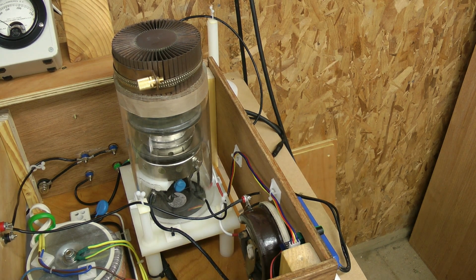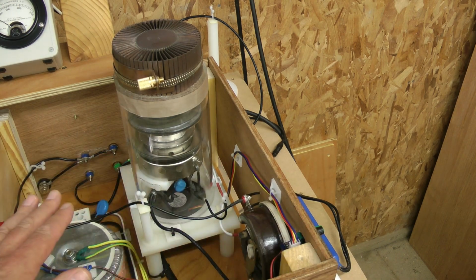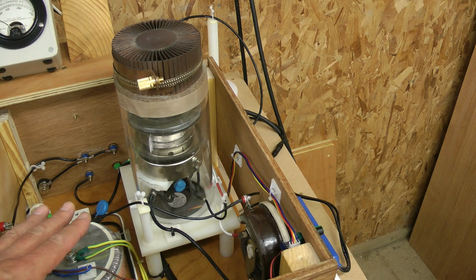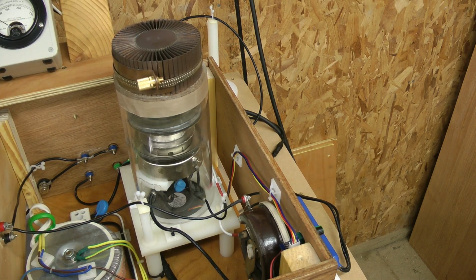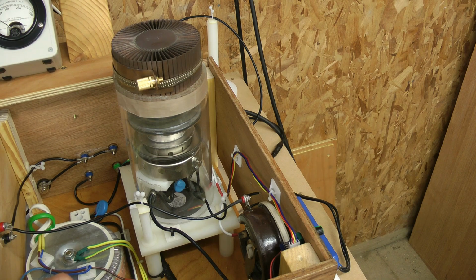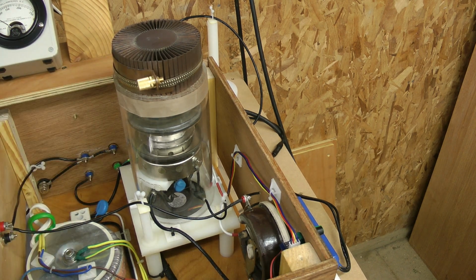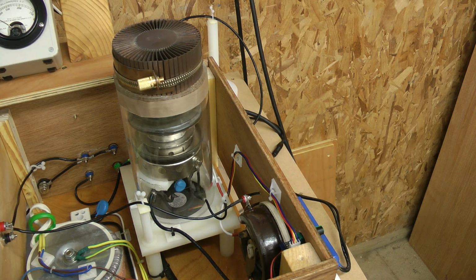So when this is running at lowest speed and it's just idling, it sits at about 60 degrees C at the anode temperature. When I'm running at full power, so say putting about 4 to 5 kilowatts of real power in, then this anode will go up to around 120 degrees C at full fan speed. If it just sits at idle at full fan speed, then you drop right down to about 60 degrees C to 40 degrees C. And at full fan speed, with 4 kilowatts of power sustained, you're running at about 120, 130 degrees C anode temperature. So the cooling is good.